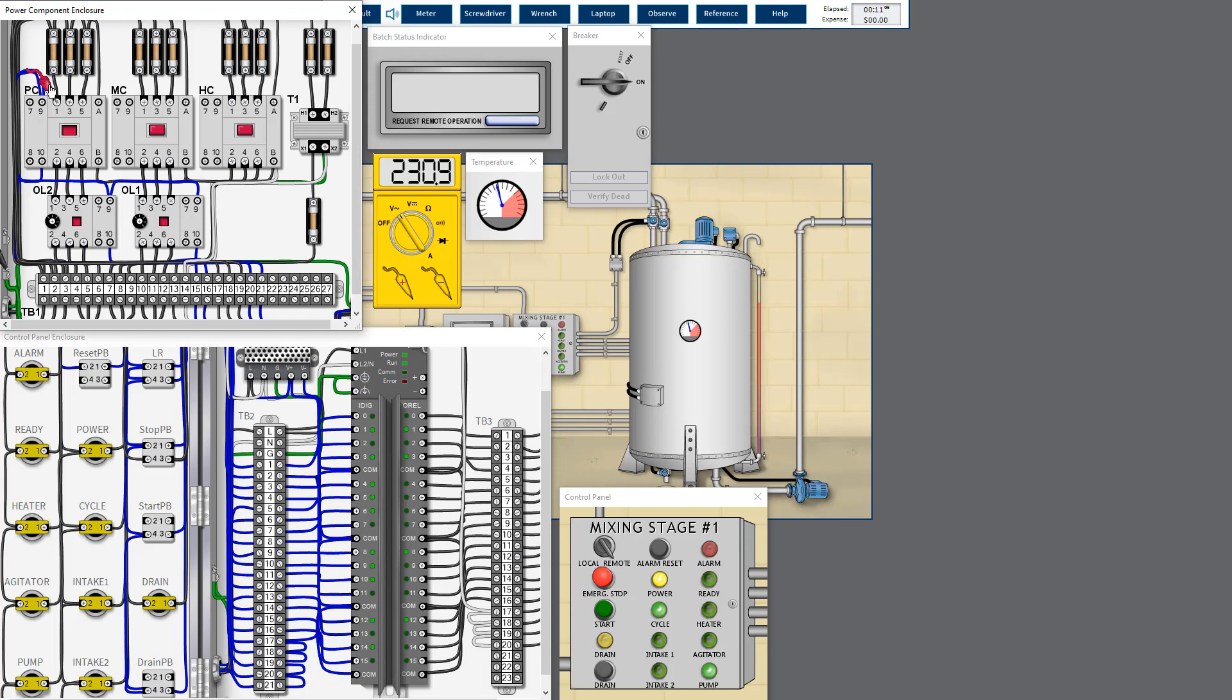So what is the problem here? Okay, one more thing I need to remind myself for three-phase circuit: the voltage measurement sometimes can be misleading. So the rule of thumb here for three-phase circuit voltage measurement is, if the line end is open, we can measure the phase voltage for individual phase.